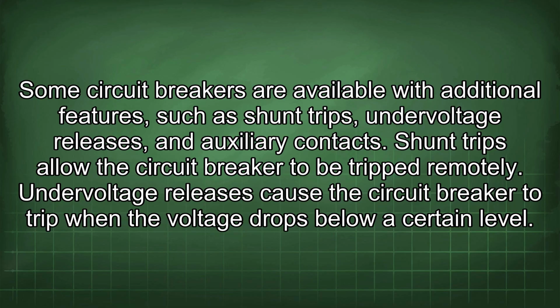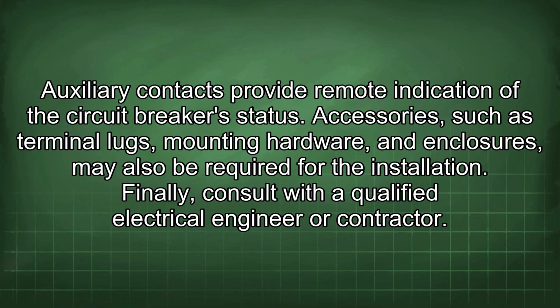Some circuit breakers are available with additional features, such as shunt trips, undervoltage releases, and auxiliary contacts. Shunt trips allow the circuit breaker to be tripped remotely. Undervoltage releases cause the circuit breaker to trip when the voltage drops below a certain level. Auxiliary contacts provide remote indication of the circuit breaker's status. Accessories such as terminal lugs, mounting hardware, and enclosures may also be required for the installation.